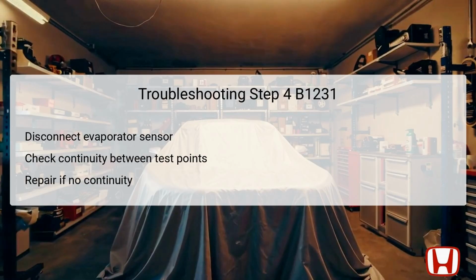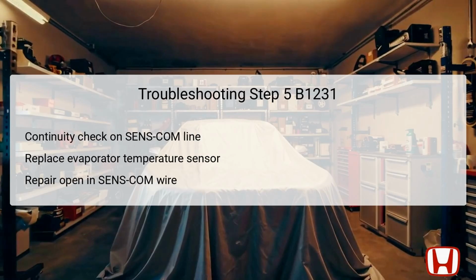However, if continuity is not present, it suggests an open circuit exists in the SENS-COM wire that requires prompt repair to restore proper signaling to the climate control system. The final troubleshooting step focuses on assessing the sens-com line continuity to ascertain whether the evaporator temperature sensor itself requires replacement. Following the same disconnection protocols, the technician should check continuity between climate control unit connector B24P number 10 and the sensor connector number 2.